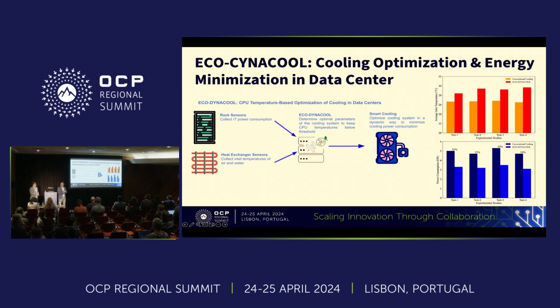As Çağatay mentioned at the beginning of the presentation, instead of focusing on the inlet temperatures inside the data center, our chip temperature-based algorithm can keep the CPU temperatures below the threshold value. So by increasing the inlet temperatures to about 28 or 29 degrees Celsius, these energy savings can be gained. This is a very critical parameter. We monitored the CPU temperatures during experimental studies, and because of the accuracy of the numerical model and experimental studies, the CPU temperatures were observed at about 78 or 79 degrees Celsius, which is so close to the threshold value.